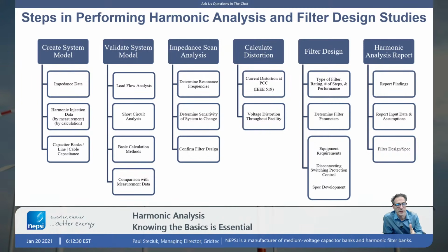We recommend some kind of validation of the system, of your model. You create a system model, you need to validate that. Validation is best done with load flow, short circuit, but some basic hand calculations is also advisable. So we're going to be talking about those in a few minutes. And then if you've taken measurements within the system, you can certainly compare your harmonic analysis output, the results, with the measurement data. Measure volts and amps within a network. Does that match my model? Run the harmonic analysis and determine if it matches.